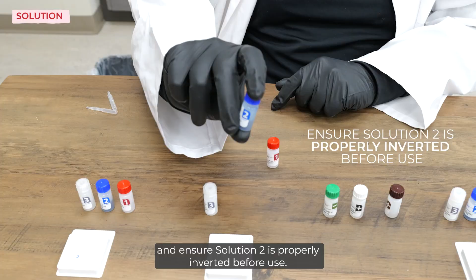The most common cause is insufficient blood collection. Other causes are failure to collect enough sample to fill to the line on the capillary pipette, inadequate mixing of blood with solution 1, or environmental conditions such as high humidity or temperature extremes that can affect membrane function. Address this by reinforcing proper blood collection technique, reviewing procedural steps, running controls to verify kit performance, and confirming the appropriate storage and testing conditions.